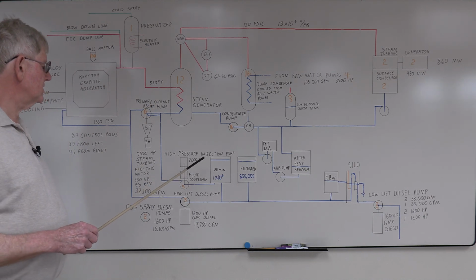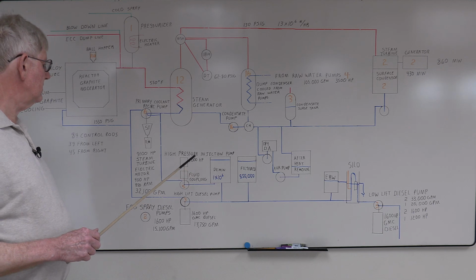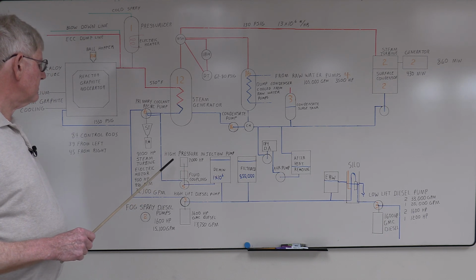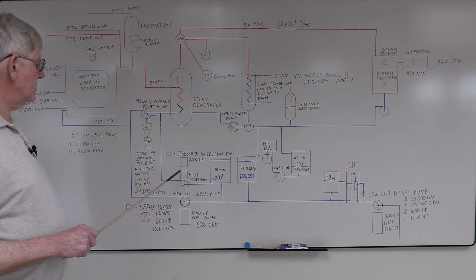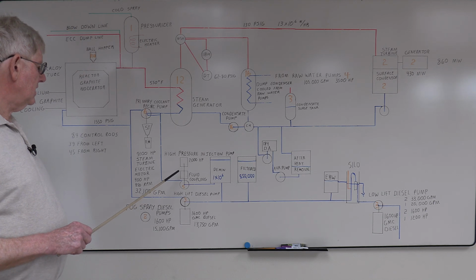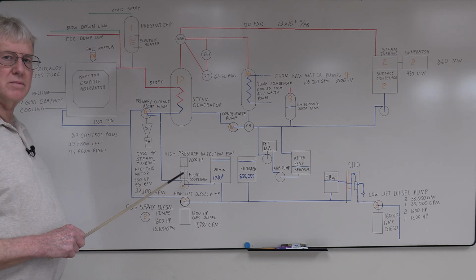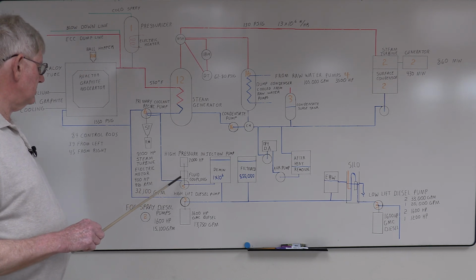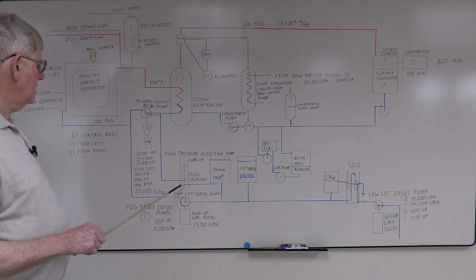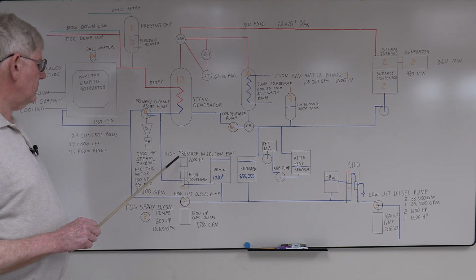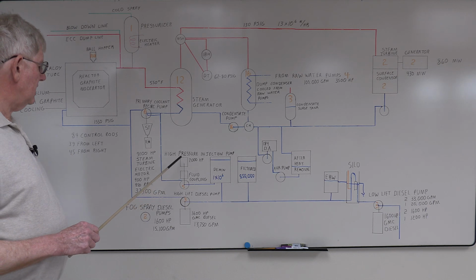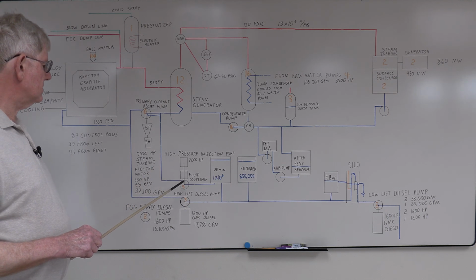You had your high-pressure injection pumps. These provided water for the reactor. They're 2,000 horsepower motors. Had a fluid coupling. It had a scoop tube. It's kind of like a torque converter. Pull oil out and it'd slow down the pump, or add oil and speed the pump up. There are 5 of these. You had to run 2 all the time. During reactor scram, 4 would start.